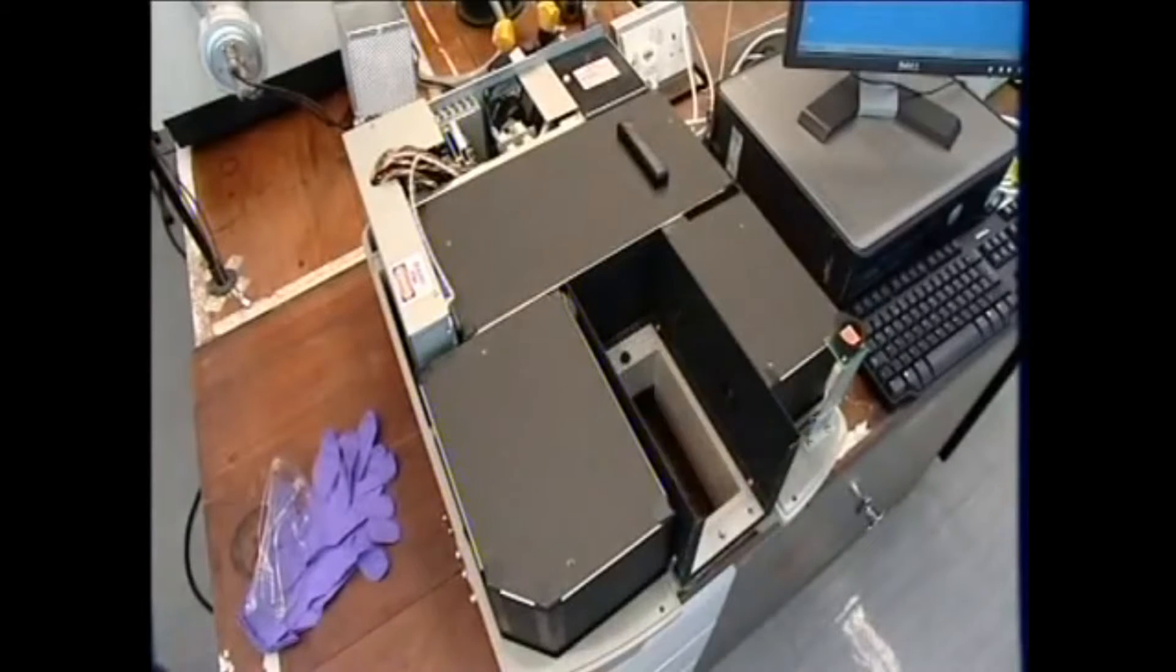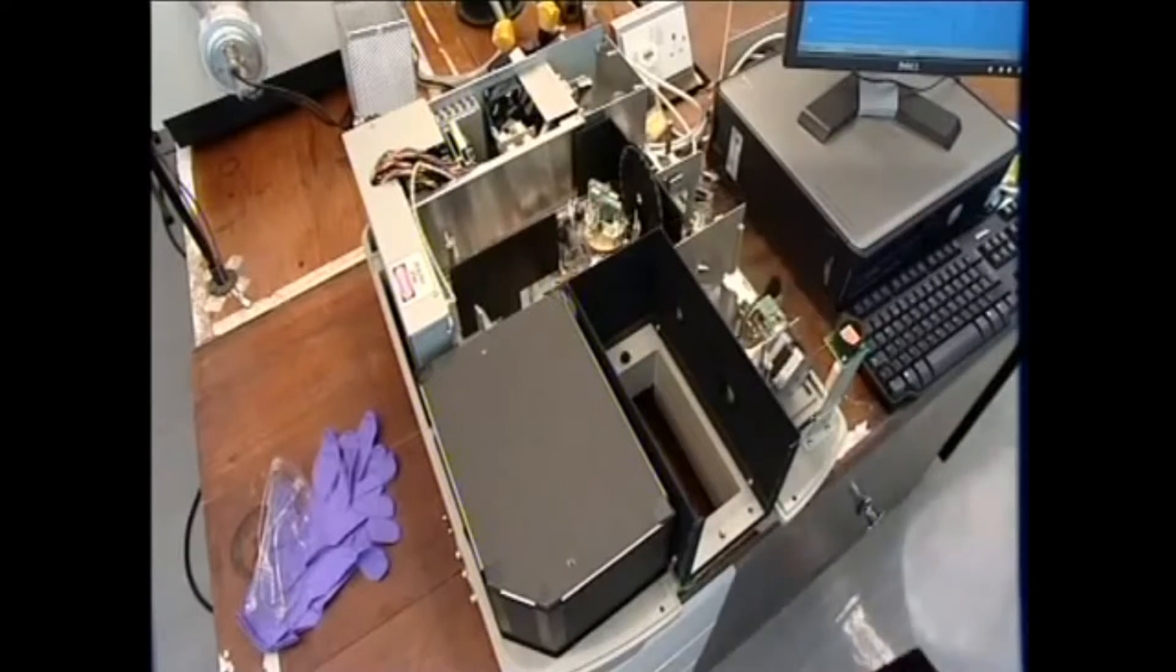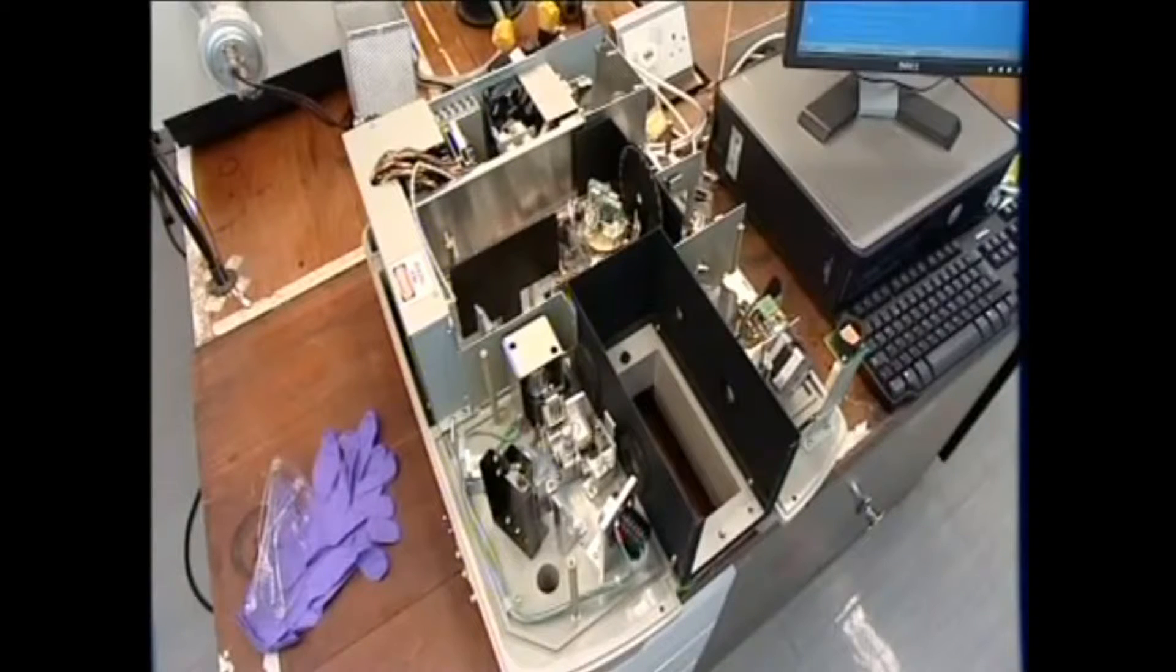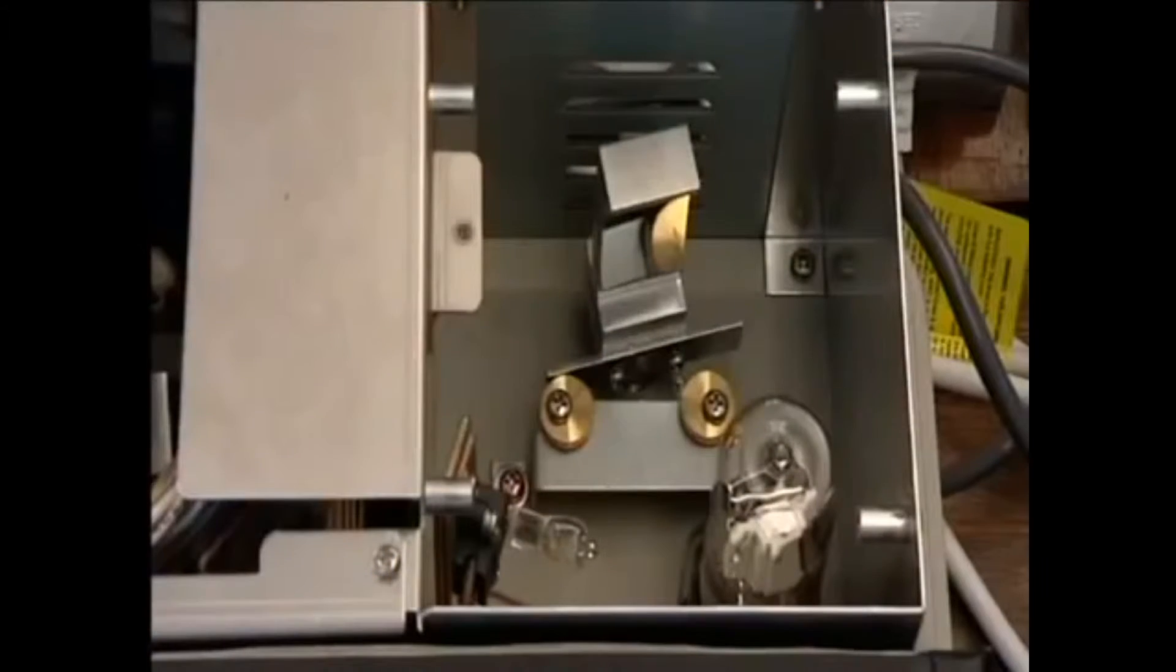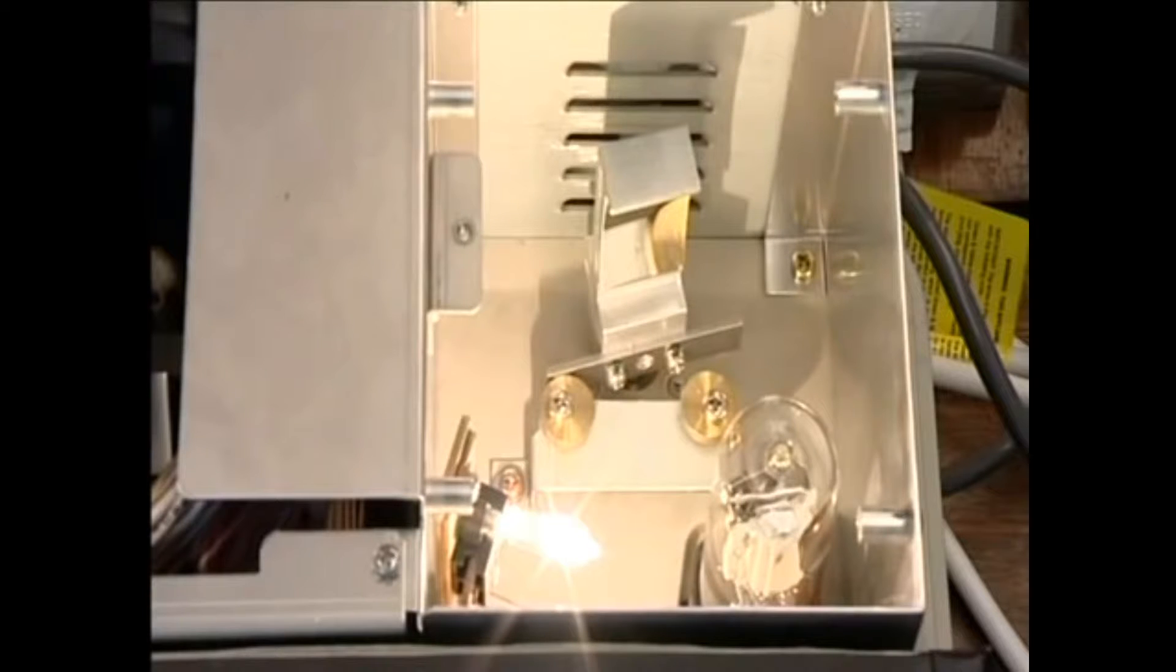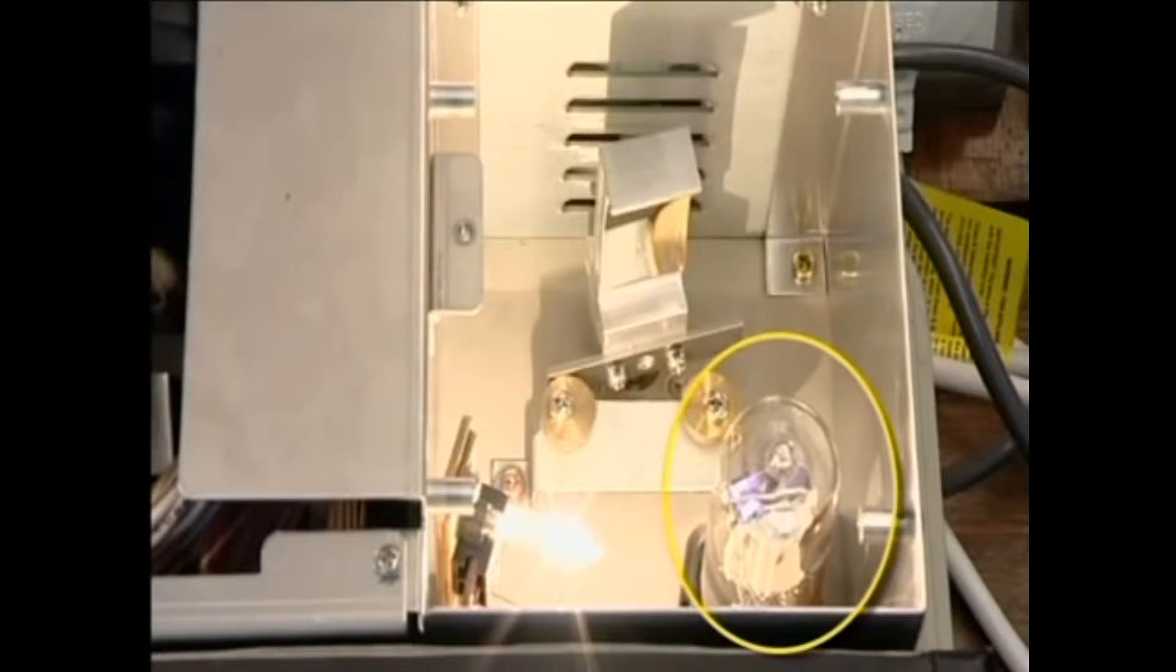Inside a UV visible spectrometer there are usually two light sources, one giving out visible light and one ultraviolet. This one is a tungsten lamp like a car headlamp bulb for the visible region and this deuterium lamp gives out ultraviolet.